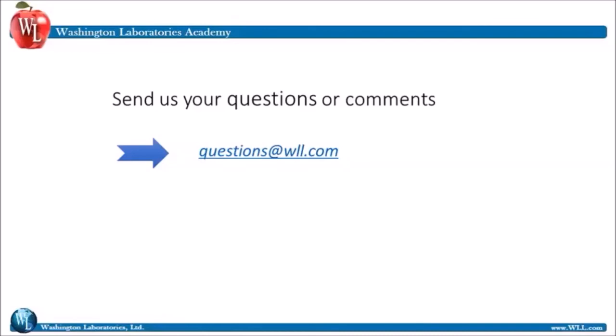Mike, to add a little bit to that, sometimes if you're experiencing this and it's dealing with cables, if you separate the wires and put one through the current probe in the reverse direction, they tend to cancel each other if they're differential. So if the level stays the same, it's common. If it deteriorates when you do that, it tends to indicate that's a differential signal. Just a little element of the test associated with that.